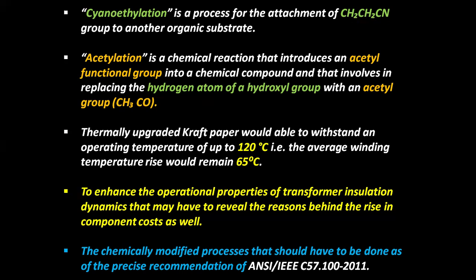Thermally upgraded kraft paper would be able to withstand an operating temperature of up to 120 degrees centigrade. That is, the average winding temperature rise would remain 65 degrees centigrade. To enhance the operational properties of transformer insulation dynamics may reveal the reasons behind the rise in component costs as well. The chemically modified processes have to be done as per the precise recommendation of ANSI or IEEE C57.100 2011.